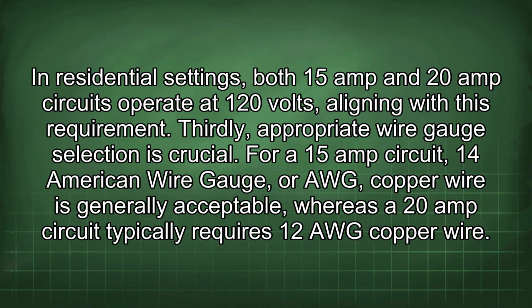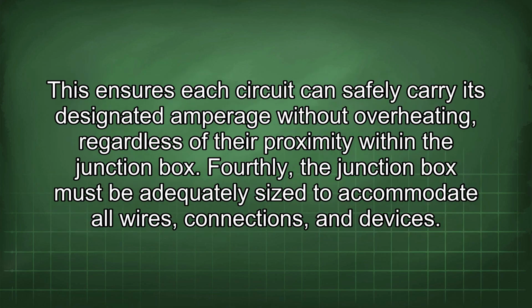Thirdly, appropriate wire gauge selection is crucial. For a 15 amp circuit, 14 American wire gauge, or AWG, copper wire is generally acceptable, whereas a 20 amp circuit typically requires 12 AWG copper wire. This ensures each circuit can safely carry its designated amperage without overheating, regardless of their proximity within the junction box.